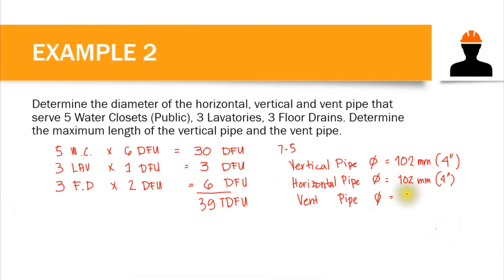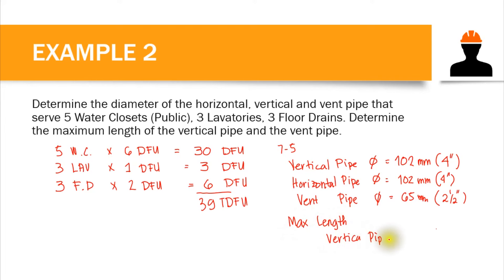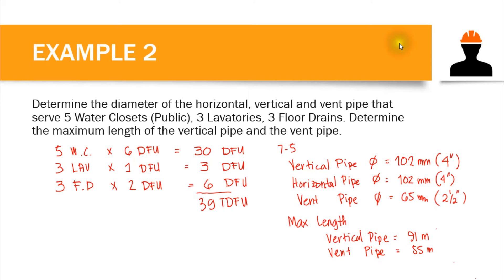To summarize example number two: the vent pipe diameter is 65 millimeters or 2 and a half inches. The maximum length of the vertical pipe is 91 meters, and the maximum length of the vent pipe is 55 meters. Those are our answers for example number two. If you have queries or questions, comment them down. Please don't forget to subscribe to my channel and hit the notification bell for more videos. Thank you for listening and God bless you.